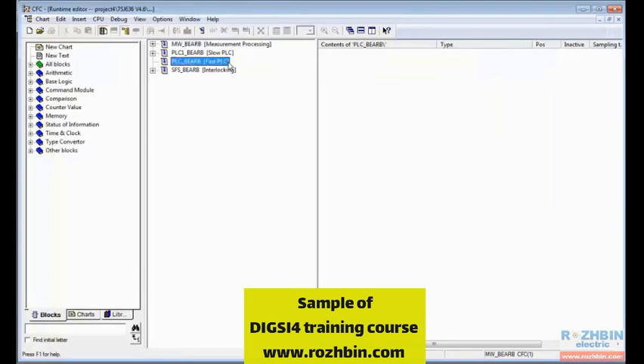The Fast PLC class has the highest priority and programs with this class are processed first. Signals relating to protection functions should be in this class. Functions defined as slow PLC have a lower priority in processing with respect to fast PLC. For example, timer and clock functions are defined as slow PLC. And generally, slow PLC can be used for any non-protection function.